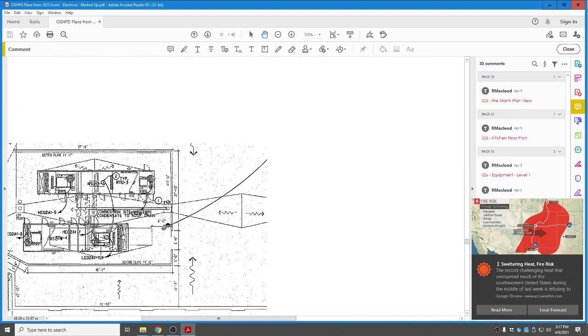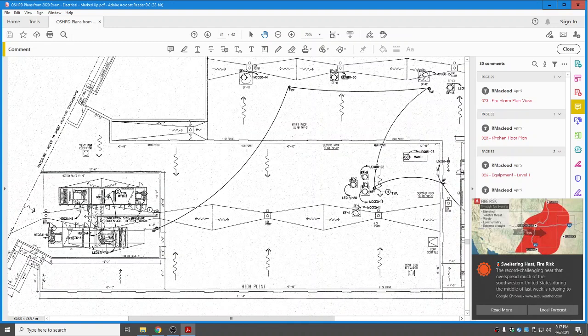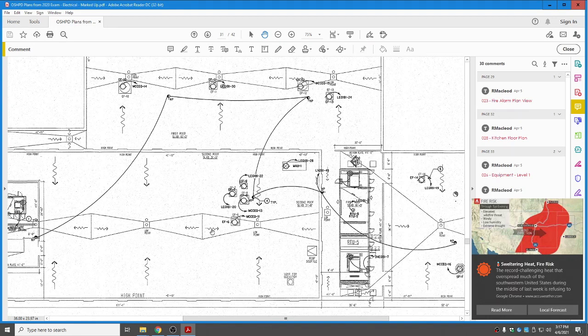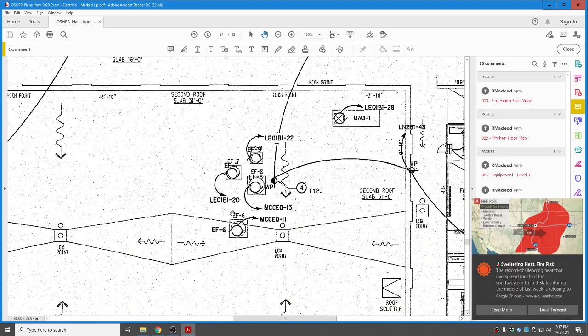Let's zoom out a little bit here and take a look what else is up here on the rooftop. Here at this end, we'll zoom in here, we have a series of exhaust fans. Exhaust fan 7 is on LEQ 1B1 circuit 20. Exhaust fan 6 is on a motor control center EQ-11. Makeup air unit is on the equipment branch, circuit 28.